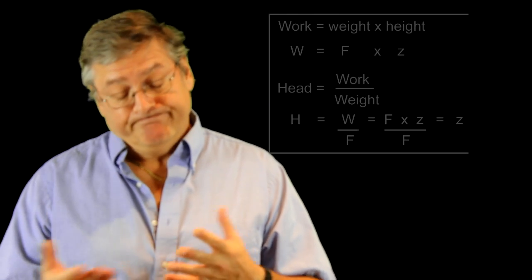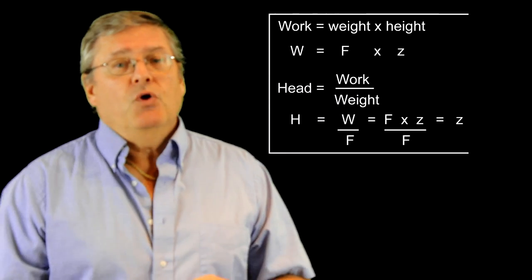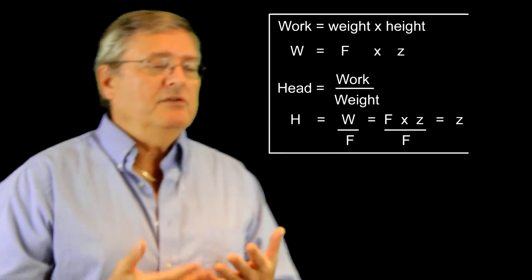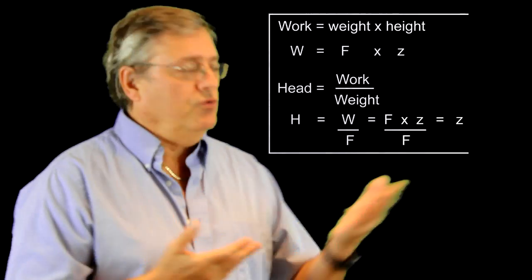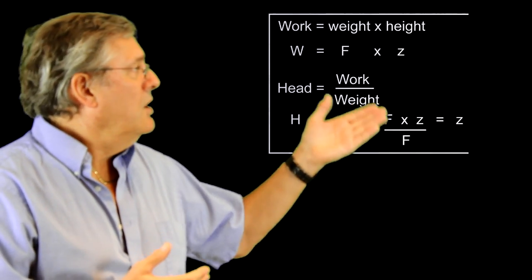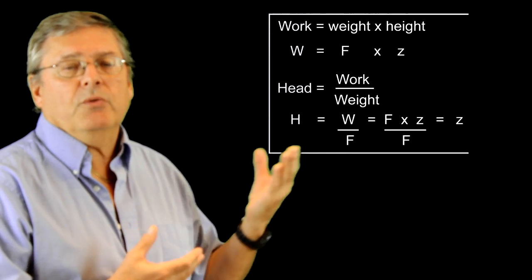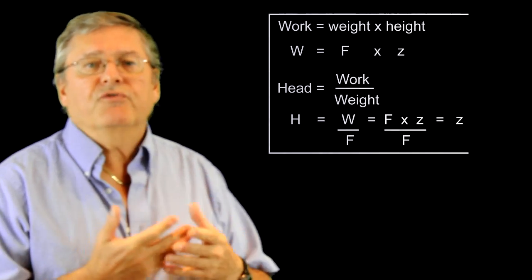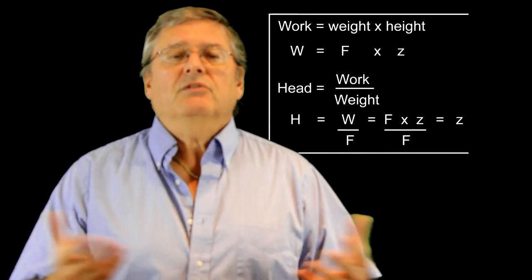So we come up with another term called head, and all head is, is the amount of work that you need to do divided by the weight of the liquid displaced. So we have work over weight that's equal to a height. So that term is now called head, and that will provide enough information to get the right size of pump. We have head and flow rate.